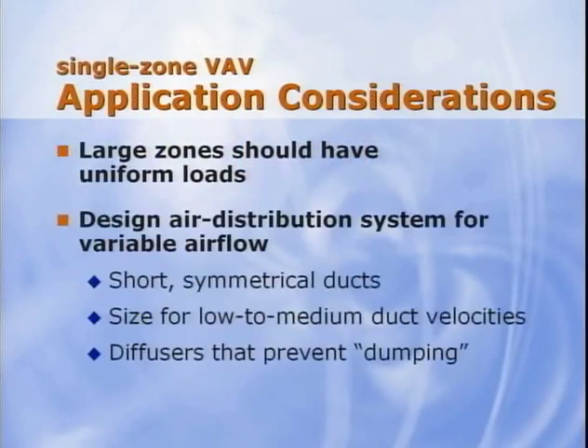Second, design the air distribution system to accommodate variable supply airflow. Keep the supply duct as short and symmetric as possible. Systems with long or asymmetric duct runs are more susceptible to unequal airflows between diffusers. Size the ducts for low to medium air velocities to minimize noise generated in the ductwork, and use diffusers that prevent dumping at low airflows.